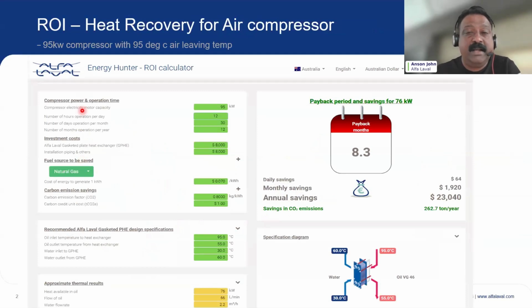So I've put in some data here. You can see if you've got a 95 kilowatt air compressor with air leaving at 95 degrees C, and let us assume it's working 12 hours a day, 30 days, 12 months. If you are adding a plate type oil cooler, the approximate price of this heat exchanger is around 8 grand, and the installation and other piping will be an additional 8 grand. This is considering the higher labor cost in Australia, and a cost of energy of 70 cents and so on. So if you are heating up the water from 30 to 60 degrees C, we are expecting a payback period of 8 months, which is pretty impressive.